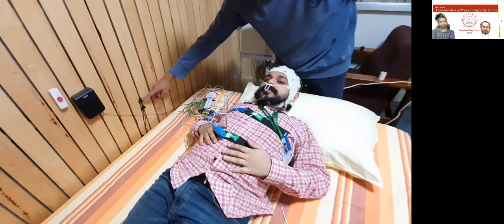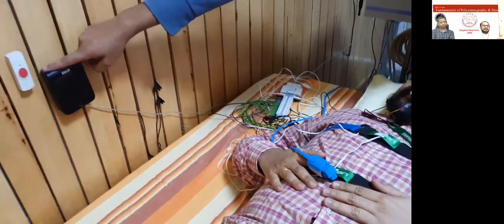So we have a microphone so that the subject can communicate to the experimenter, and there is a speaker through which the experimenter can communicate to the subject, and there is an emergency alarm bell. In case the subject wants to go to the washroom, we will instruct them to simply press the bell. The experimenter will come and detach the subject from the junction box so that he or she can go to the washroom safely. Otherwise, they will try to wake up, and in that process, they will pull the electrodes and the study will go for a toss. So it's very important to have these things and instruct the subject accordingly.